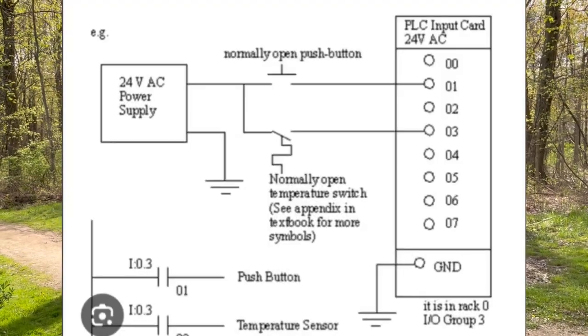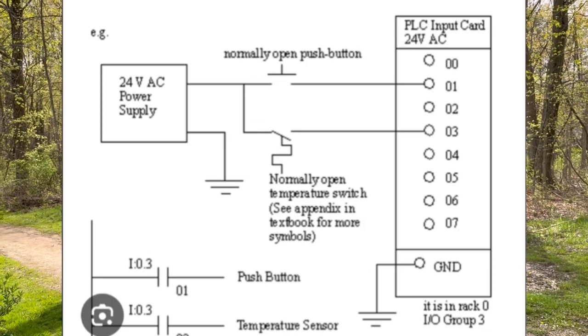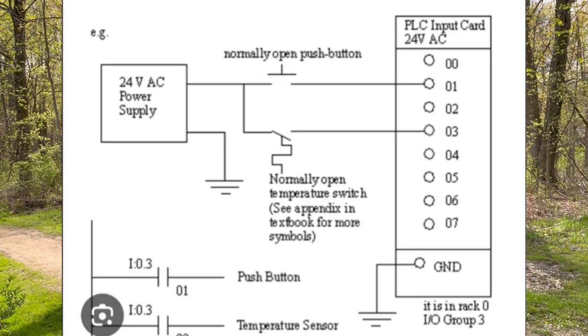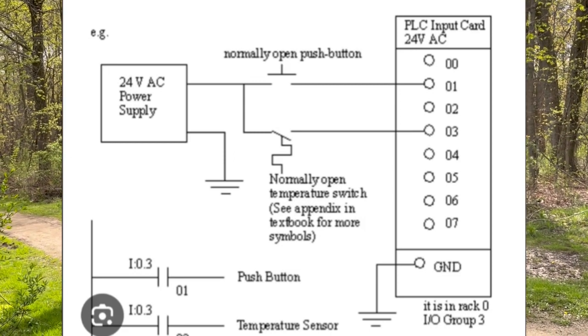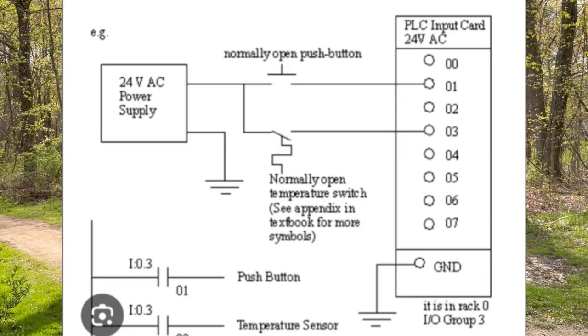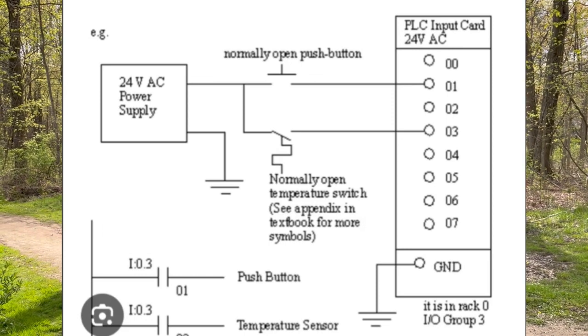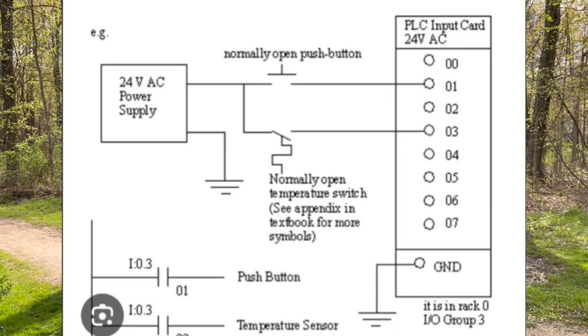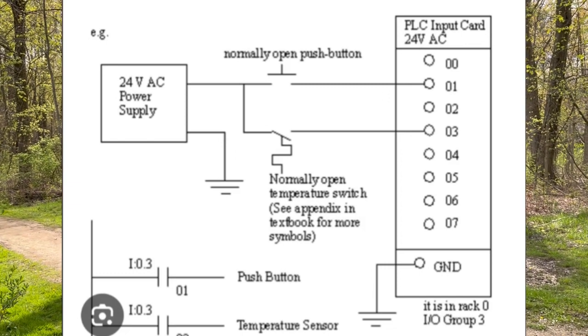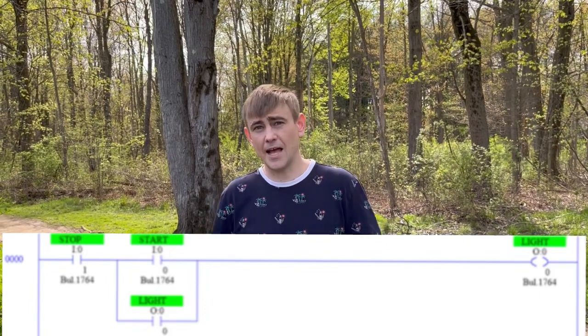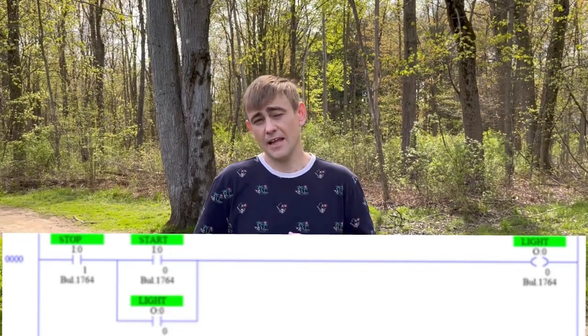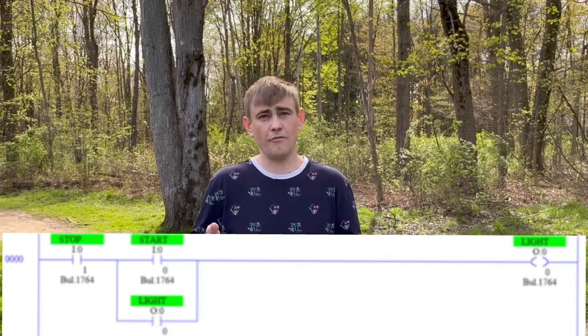So if you're using a normally open push button as a discrete input to a PLC, you would wire a power source to one terminal of the normally open push button. That power, whether it be 120 or 24 volts DC, would end where the push button is. Then when you push in that push button, it would energize through the push button into input 0-1 on your PLC. The power goes into that input terminal on the discrete input module, that input shows active in your PLC logic, and you use that input in your programming to make decisions and turn discrete outputs on or off.